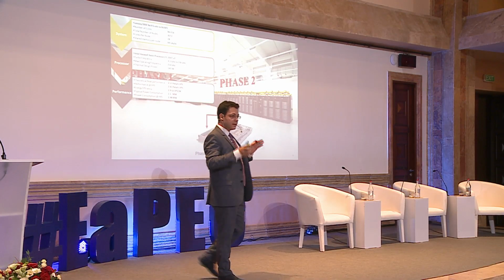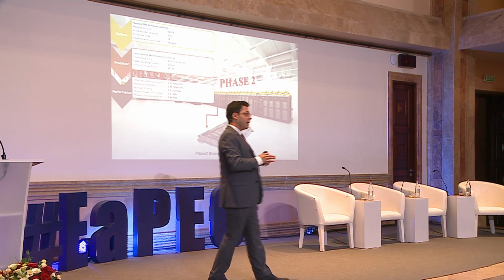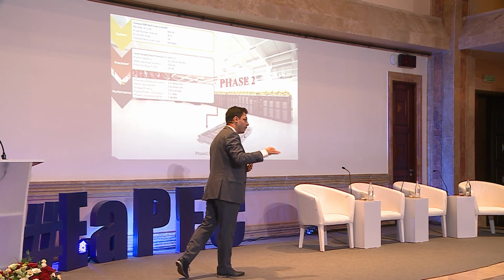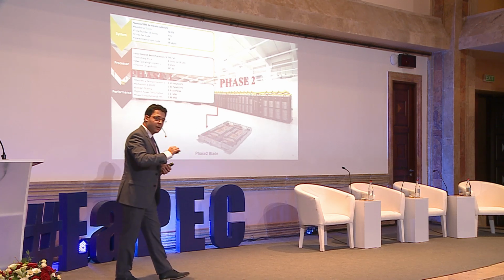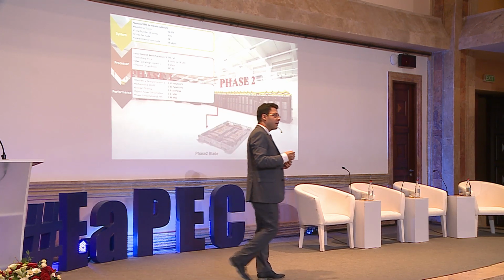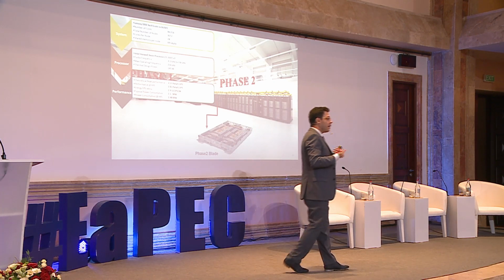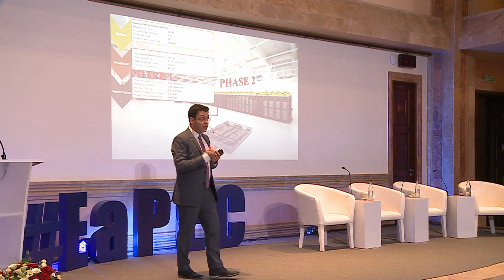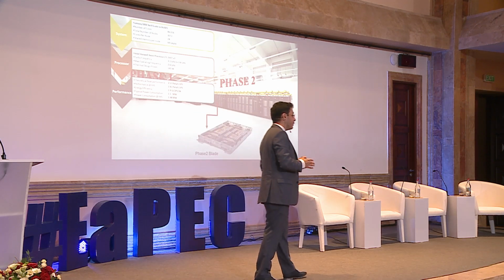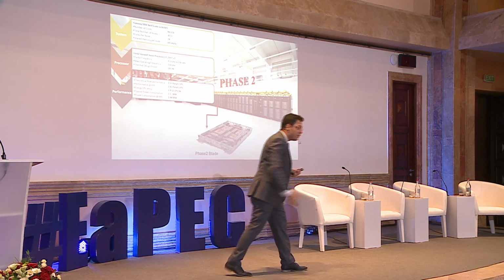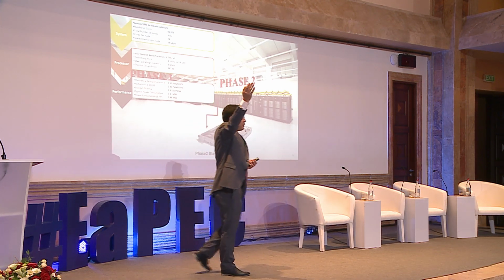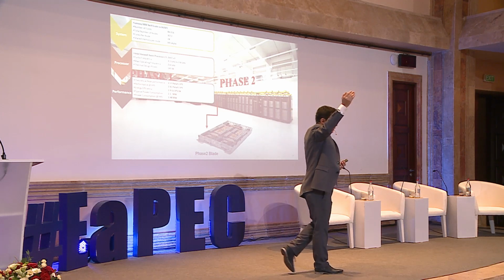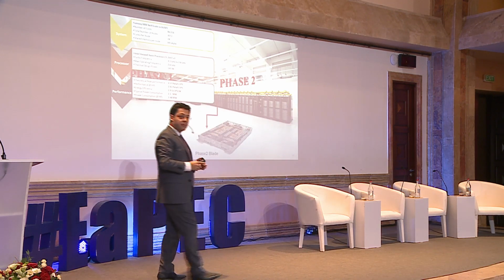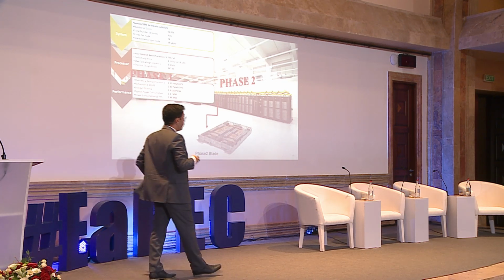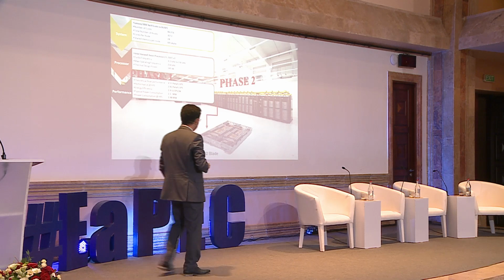By telling you SuperMUC is a directly warm water cooled system, I mean its active components, like processor and memory, are directly cooled by water with temperatures up to 45 degrees C. Can you imagine that? This allows us to do free cooling, so we don't use any refrigerators or chillers. We pipe the water to the roof, use the outside temperature all year round, in winter and summer, then pipe that water back into the system, withstanding inlet temperatures of up to 45 degrees C.